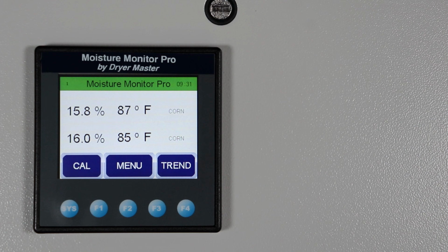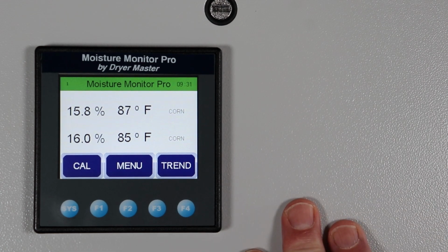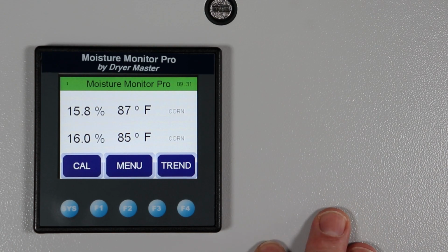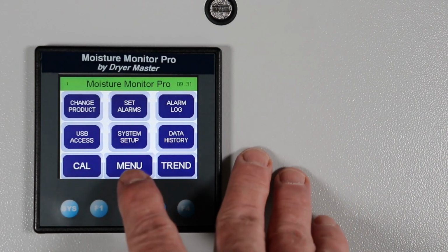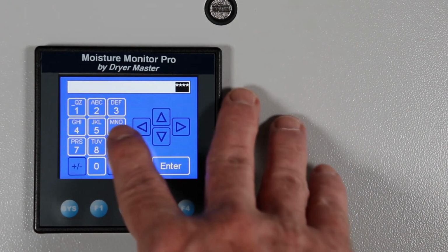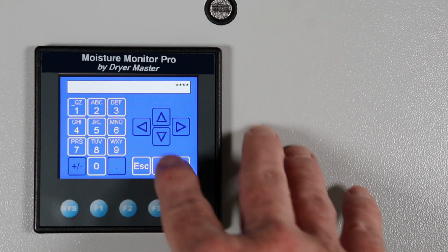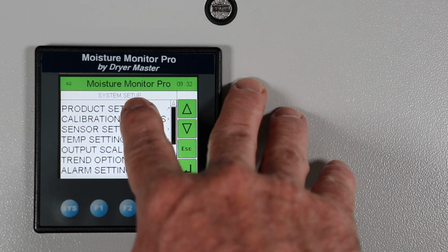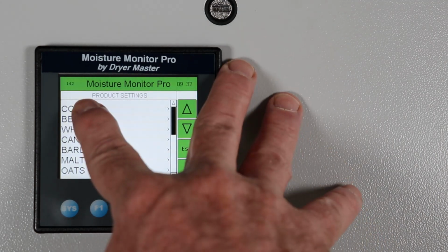Now we have a schedule in the manual with some suggested multiplier values. We call it, the multiplier we call a slope. I just want to show you very quickly, most times you will not have to adjust this. There are just some default values in there. But this is one thing you might want to look at if you are seeing the sensor having any problem with calibration. Okay, so the way to do this is really quite straightforward. Menu, System Setup, Password, and it's under Product Settings. And we're going to, for example, corn.